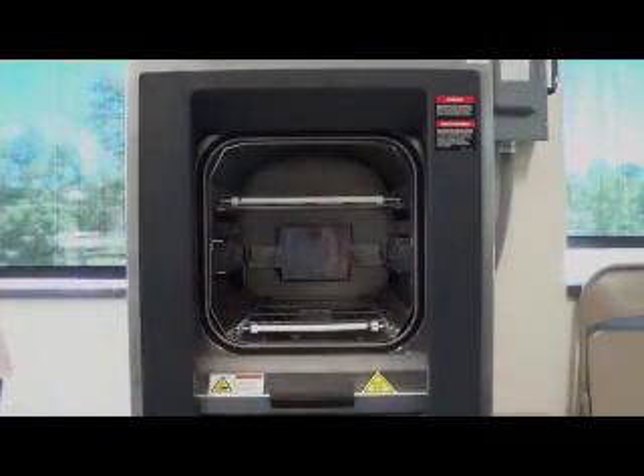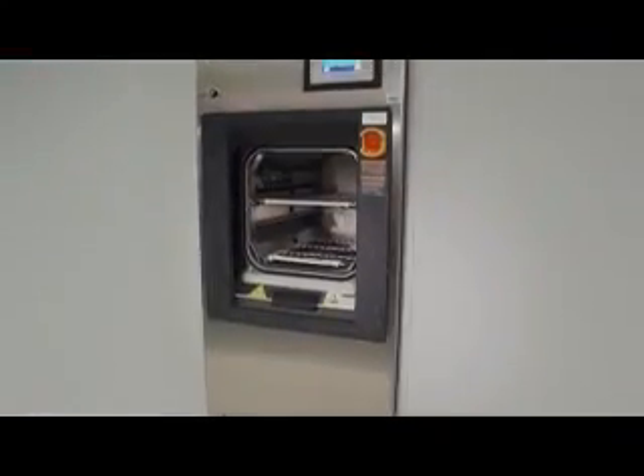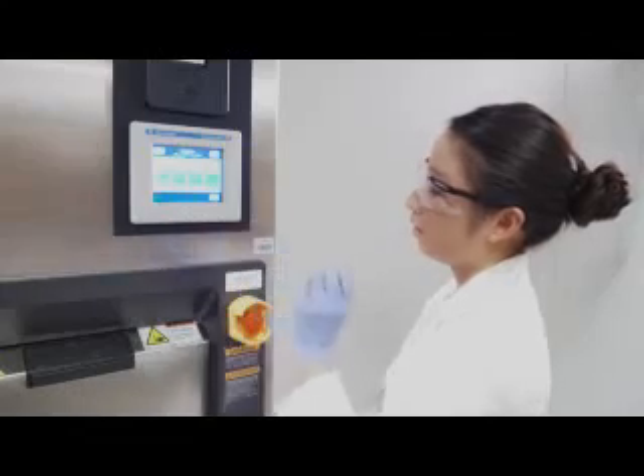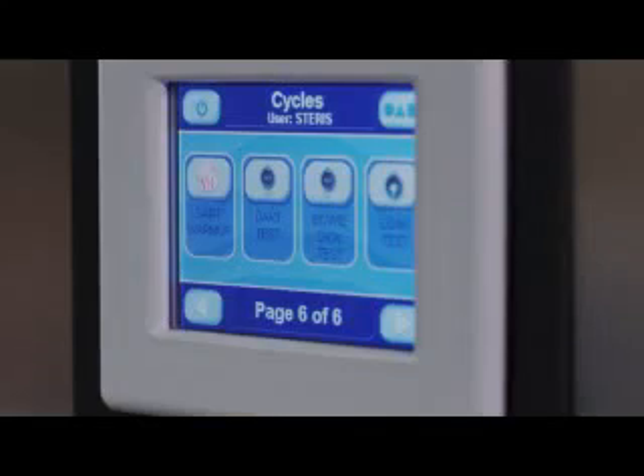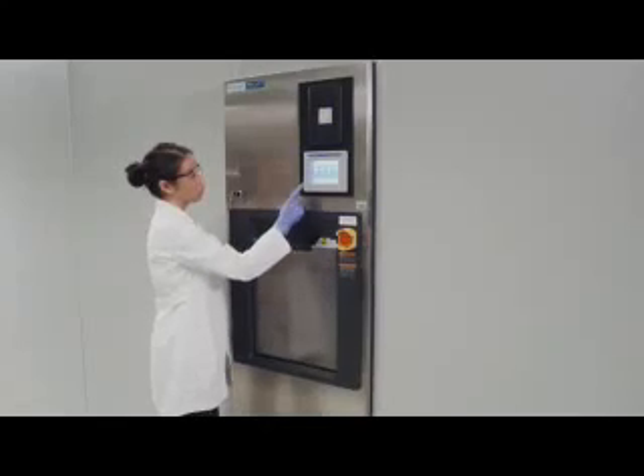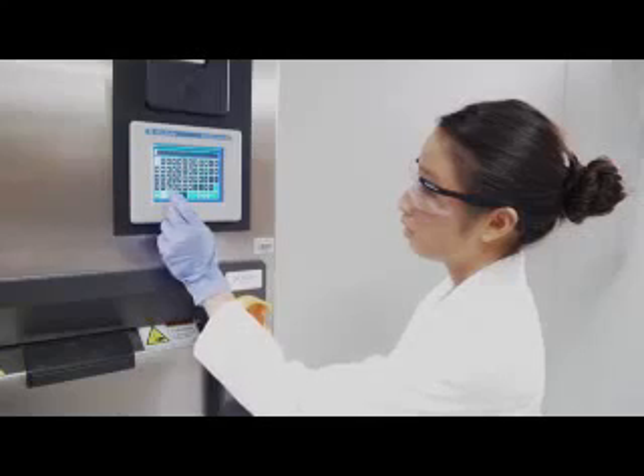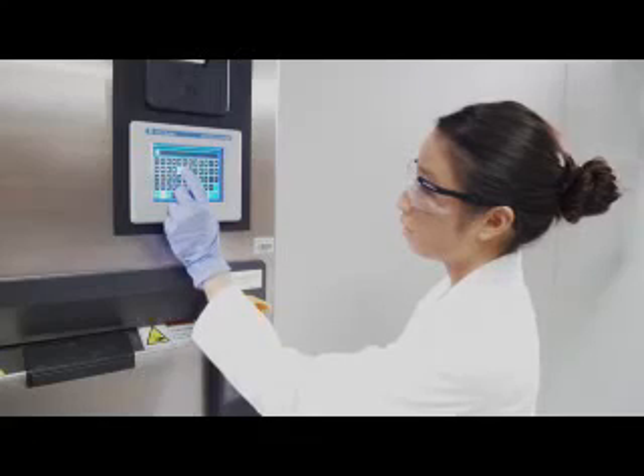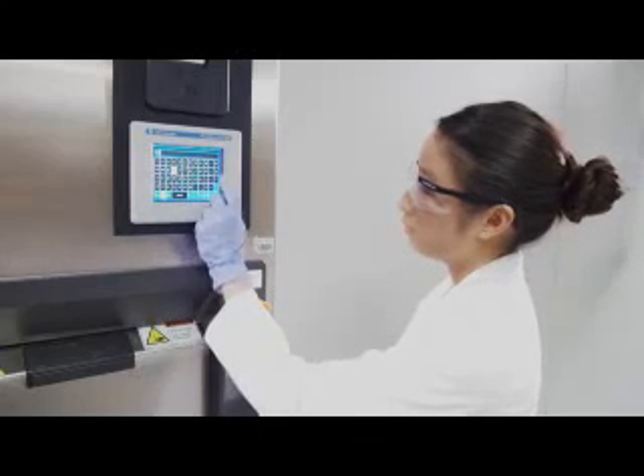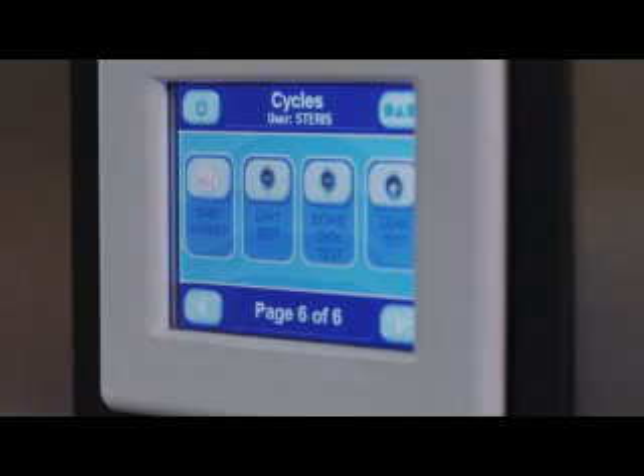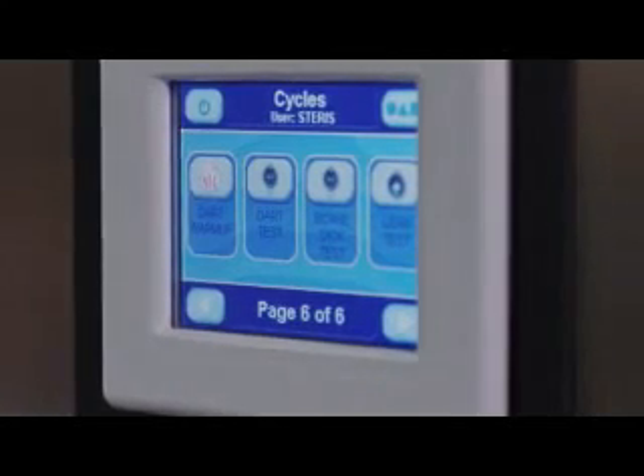minimal force to operate. The AMSCO Lab Series sterilizer is equipped with a programmable logic control and a color touchscreen interface. This user-friendly interface allows the operator to create passwords, define user access levels, program sterilization cycle parameters, and perform DART, Bowie-Dick, or leak tests.